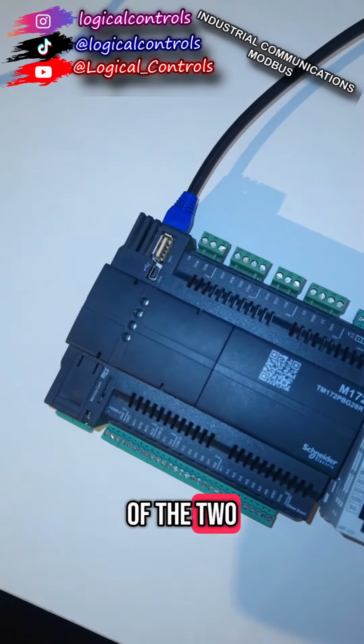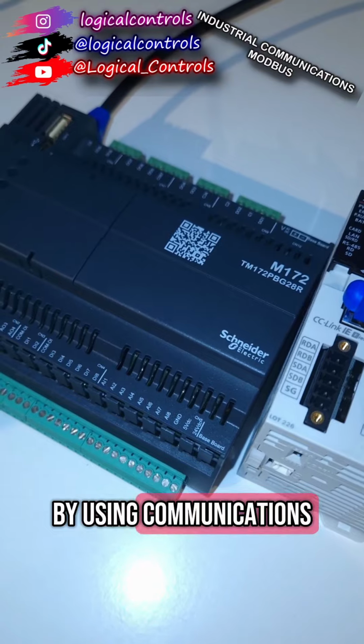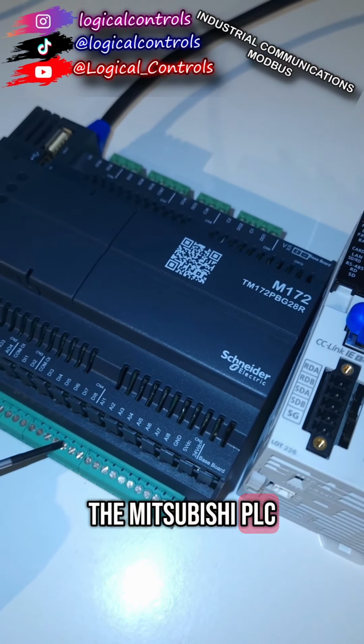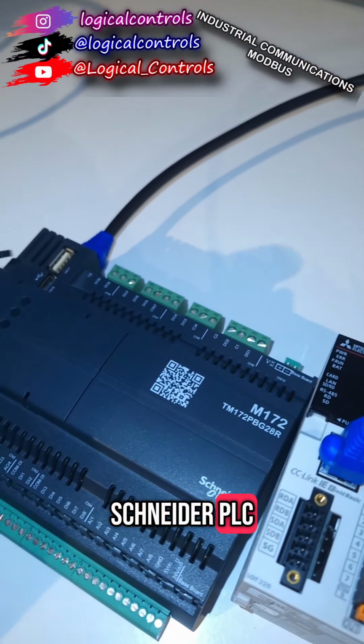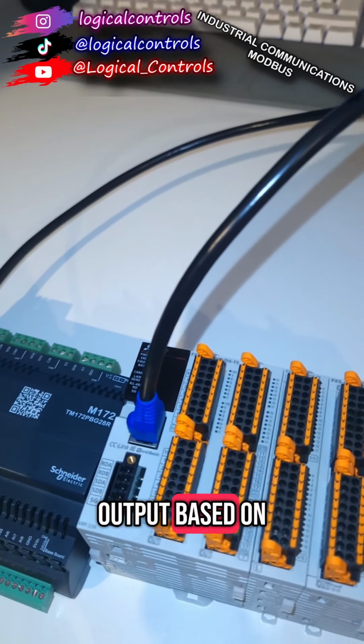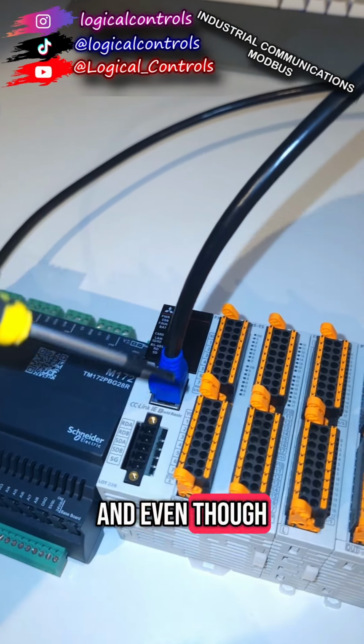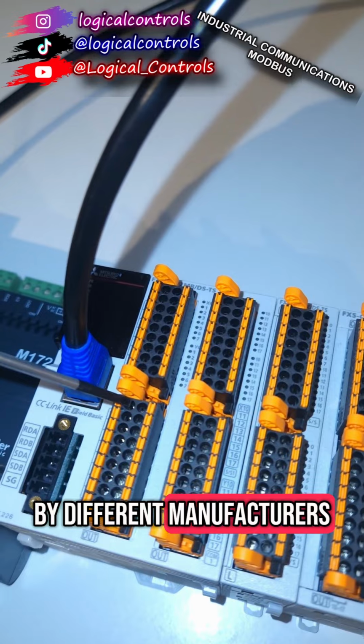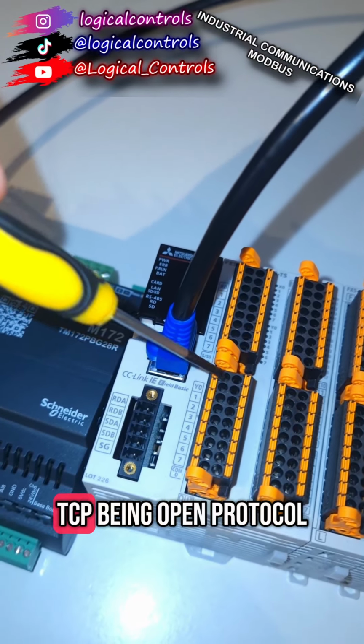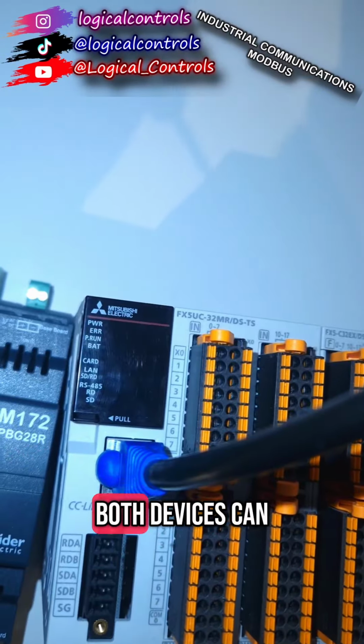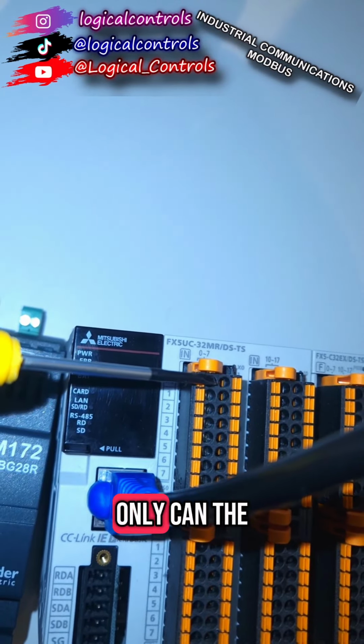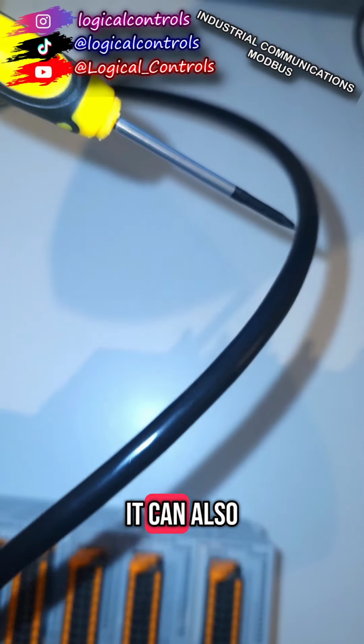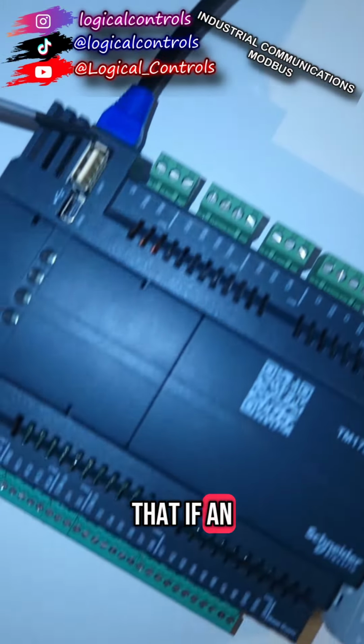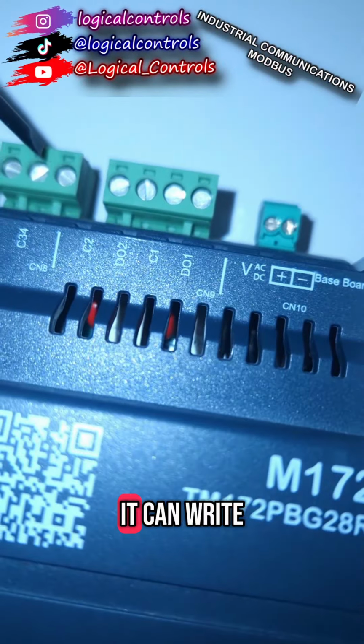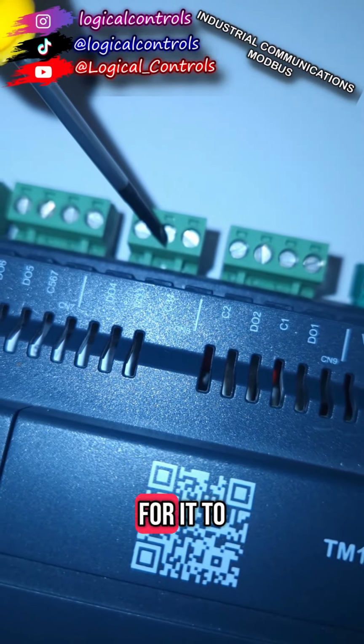In the case of the two PLCs I've got here, by using communications, the Mitsubishi PLC can read the input of the Schneider PLC and activate an output based on this input data. And even though both devices are by different manufacturers, due to the nature of Modbus TCP being open protocol, both devices can use it. Not only can the Mitsubishi read the data, it can also write data, meaning that if an input activates on the Mitsubishi, it can write to a bit in the Schneider for it to activate an output.